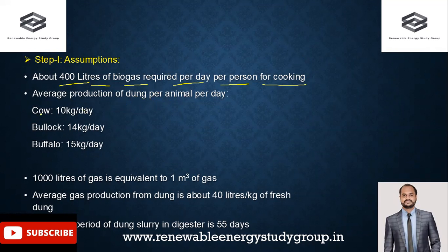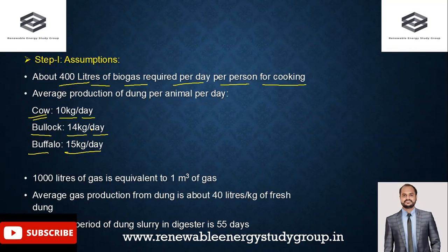For average production of cattle dung on a per-animal basis: a cow produces 10 kg per day, a bullock produces 14 kg per day, and a buffalo produces 15 kg per day. When designing or installing a biogas plant, we must ensure we have the requisite supply of cattle dung as slurry. Also, 1000 liters of gas is equivalent to 1 cubic meter of gas.